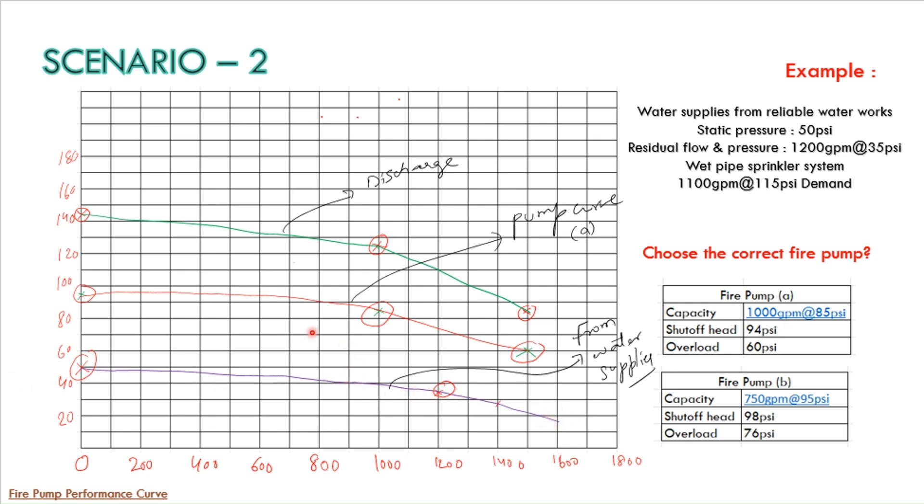Apart from that we have also taken the details of option A fire pump and marked here. If you see 1000 GPM at 85 PSI the marking is here and with shutoff at 94 PSI and overload 1500 GPM at 60 PSI.